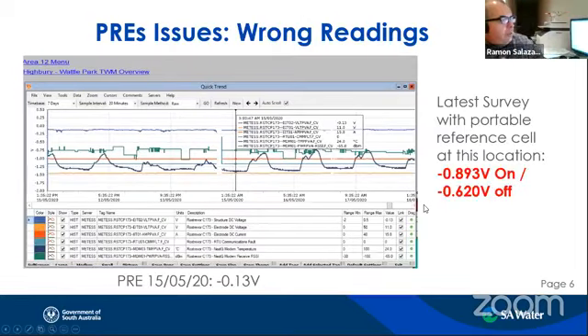And this is another example, on another water main. The reference electrode is measuring minus 0.13 volts, but the latest survey at that particular location was 0.893 volts on, 0.620 volts off. So obviously this 0.13 volts is really, really far from the point. And you see there's a straight line here that doesn't have much change. So the question is, what's going on here? Is it just because it's dried out? Can we reactivate the reference electrode, or is there a problem, probably a broken cable? That's why we need to investigate this.